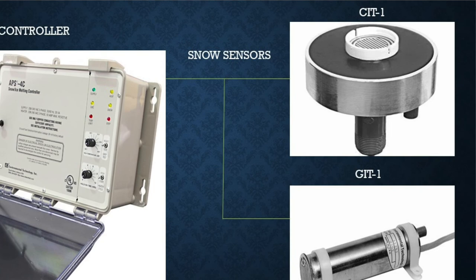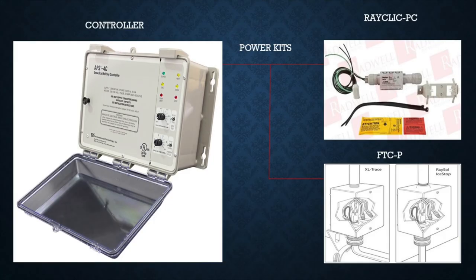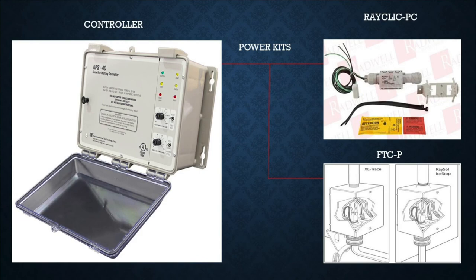The CIT sensor must meet two criteria to energize: temperature at or below 38°F and moisture present in the cup. The second sensor is a GIT — a gutter sensor — which also requires 38°F or below with moisture on the sensor before energizing the controller. From the controller you run to a power connection kit. The main options include the RAYCLIC-PC for familiar installations and a heat-shrinkable weatherproof option called the FTC-P. An end seal — the RAYCLIC-E — is used at the cable end.